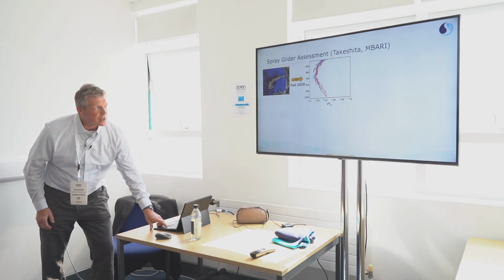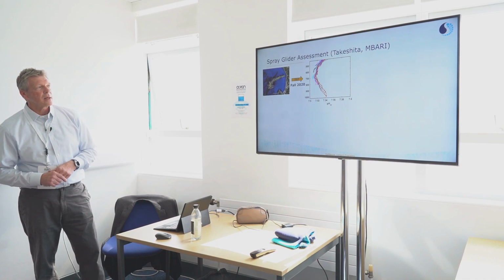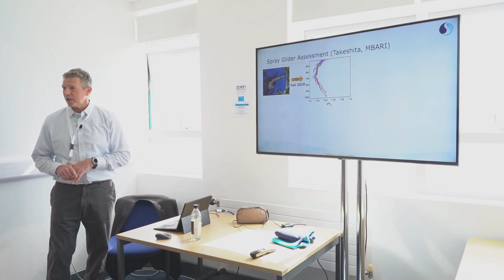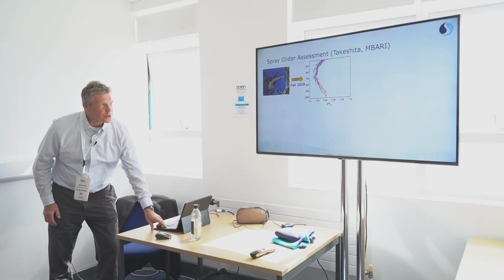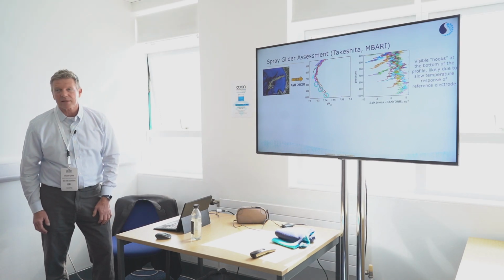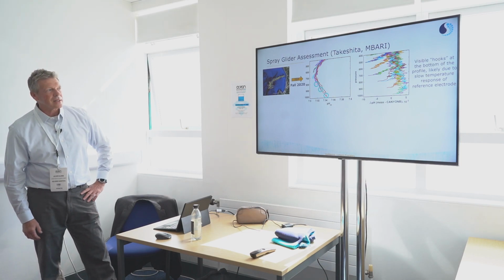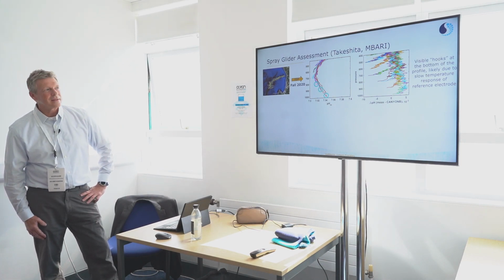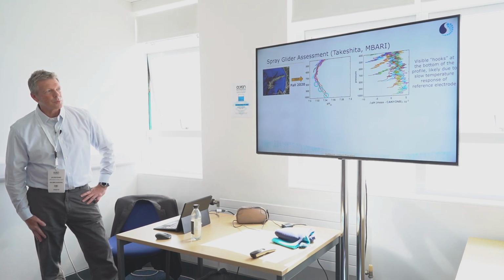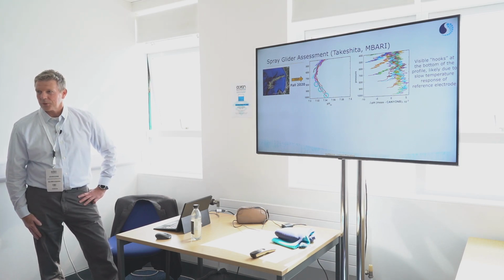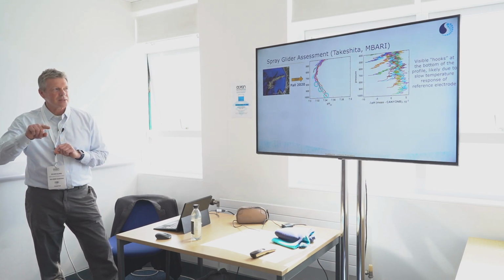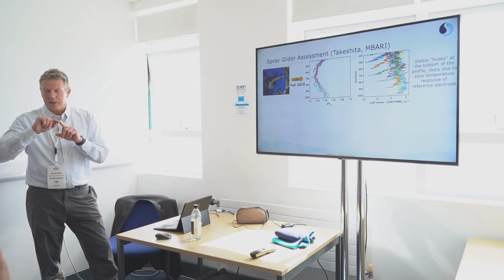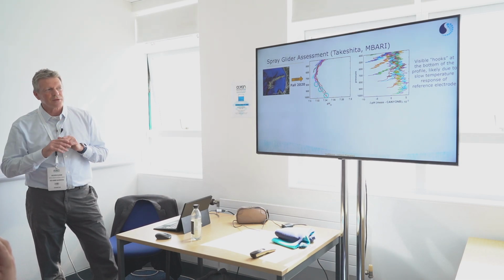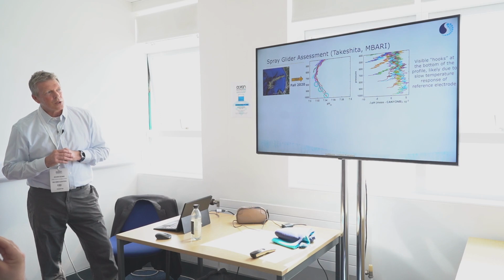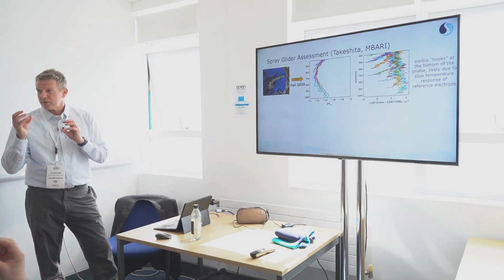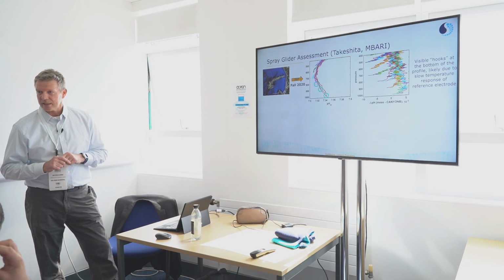One thing we noticed during this glider deployment, which we hadn't done before, was some interesting features in the profiles. At the end of the profile, you can see where the green circles are, these little hooks. That's basically what we call hysteresis effects - as you're going up, the time response of the sensor isn't well characterized, and it's not responding fast enough. We attribute this not to the ISFET component, but to the reference component of the sensing element.